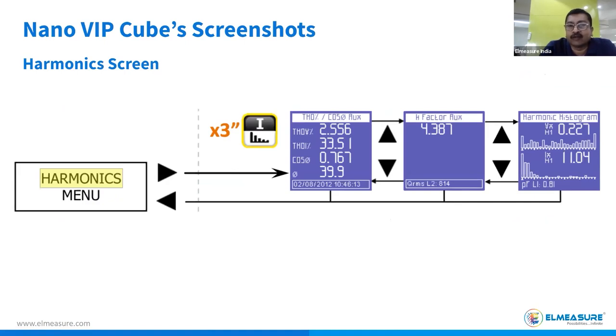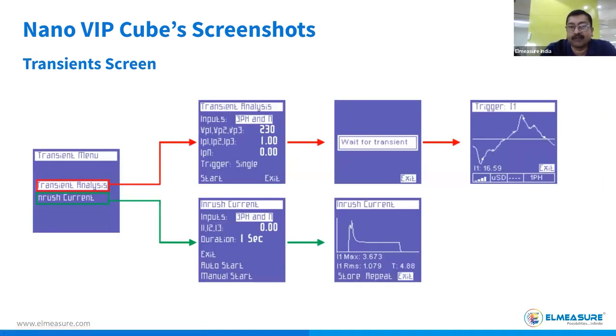This is the harmonics thing. We tried to take some snapshots using this meter in the display itself, so you get THD, voltage, current, and power factor. This is generally with respect to the aux voltage we talked about. On the right side you can see bar graphs in terms of patterns, various types, so you can choose with respect to the harmonics of voltage and current. You get the data, and the bars show their own peak, so you can understand where there is trouble happening with respect to power quality. This is the transients and everything available in the product, including inrush current.